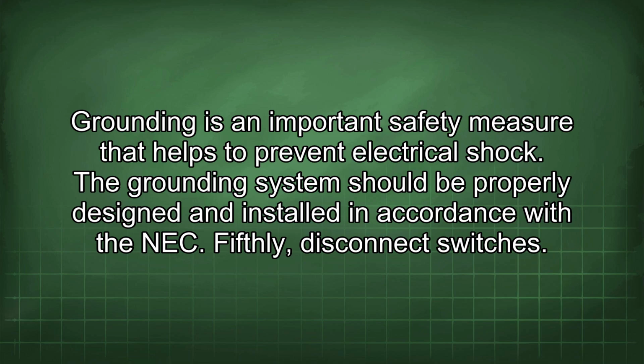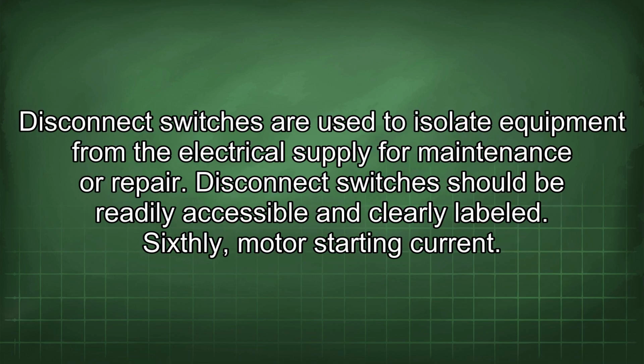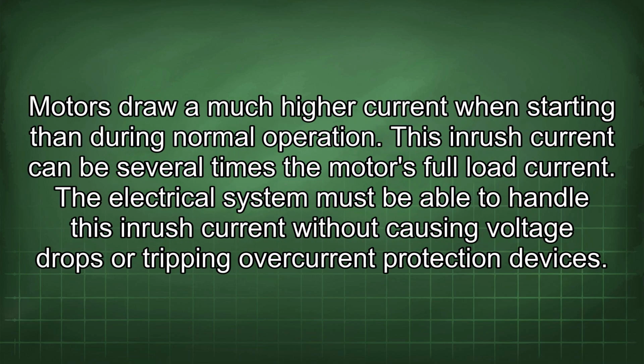Fifthly, disconnect switches. Disconnect switches are used to isolate equipment from the electrical supply for maintenance or repair. Disconnect switches should be readily accessible and clearly labeled. Sixthly, motor starting current. Motors draw a much higher current when starting than during normal operation. This inrush current can be several times the motor's full load current.